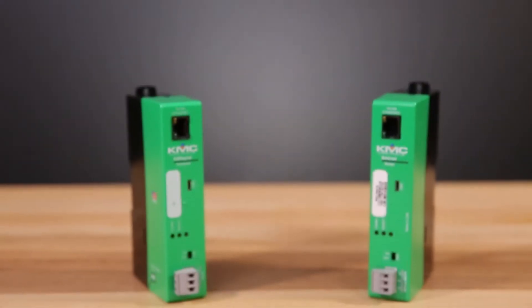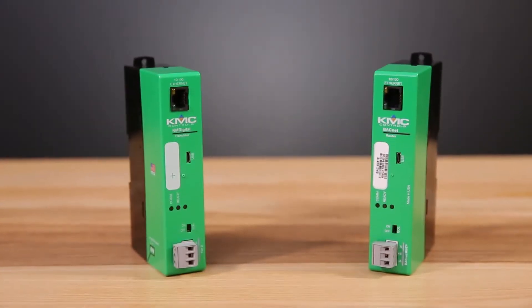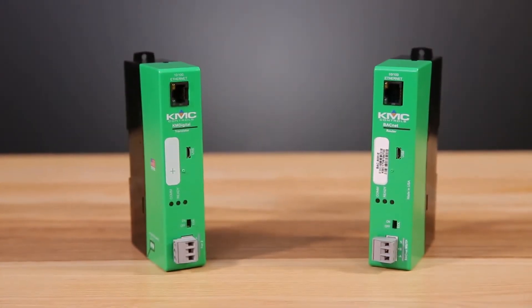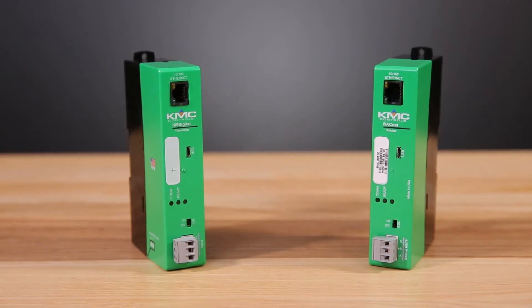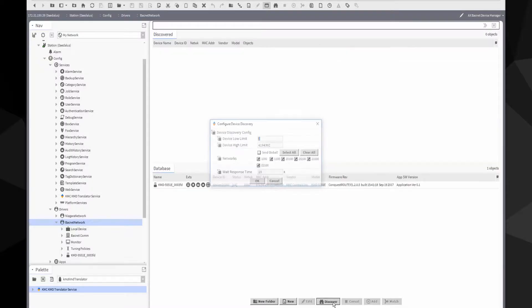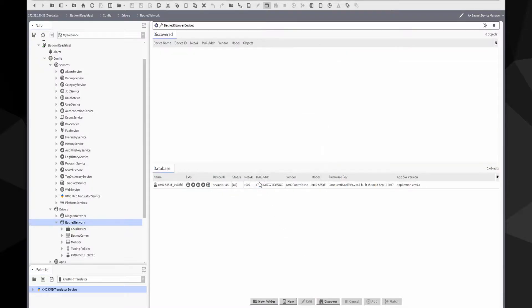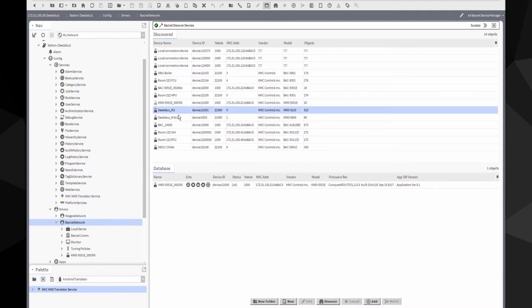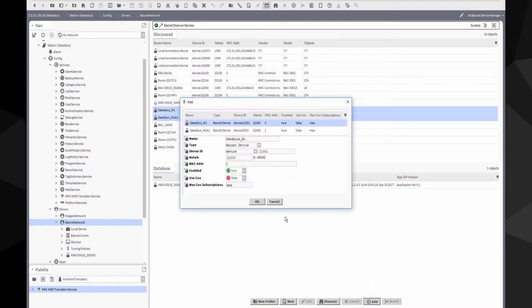The Translator, which looks similar to KMC Conquest BACnet router, is installed on a KM Digital network. It discovers the KMD devices and creates a virtual BACnet device for each KMD controller. The virtual network of devices are then available for discovery.